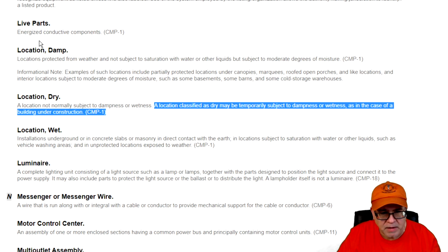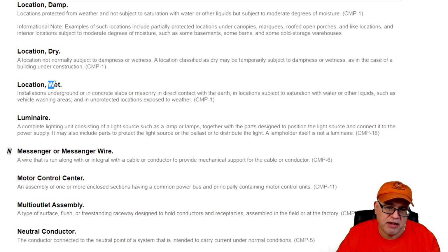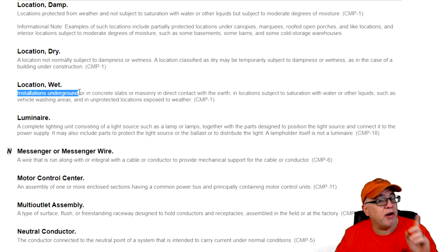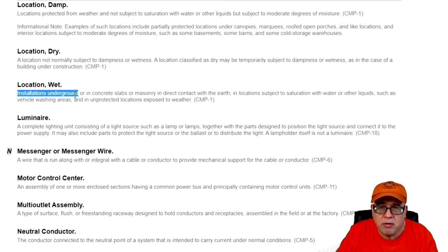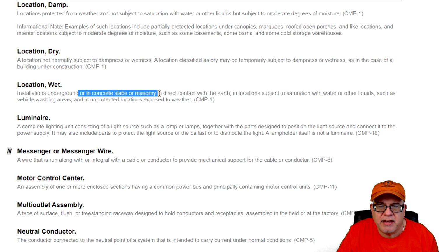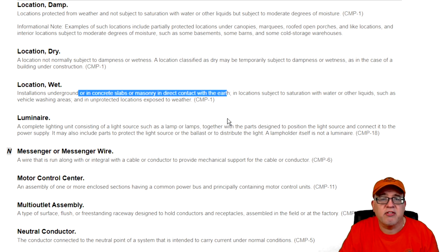Okay. Next, a wet location. What is it? Installed underground. So all underground installations are wet locations. Remember that. It doesn't matter if the raceway is a sealed up PVC and you think that it's going to stay dry in there. It's not. Also, any concrete slab or masonry that is in direct contact with the earth, slab on grade, any of that raceway, any of that conduit, any of that that's installed, is considered a wet location. Keep that in mind.